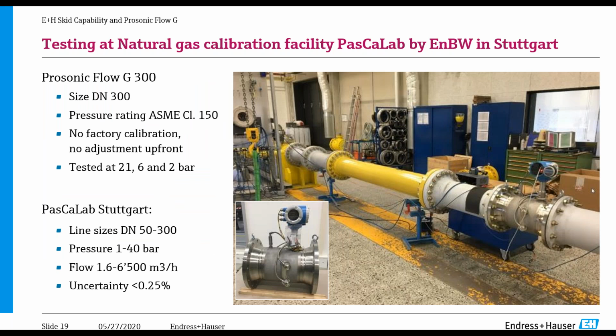So obviously the meter is new, but we had to do some testing beforehand. And what we did here is we tested a DN300, so 12-inch meter, at a place called PasCaLab in Stuttgart, Germany, on natural gas. We sent it there before we had our calibration rig that I showed you earlier. So this meter actually went out uncalibrated.